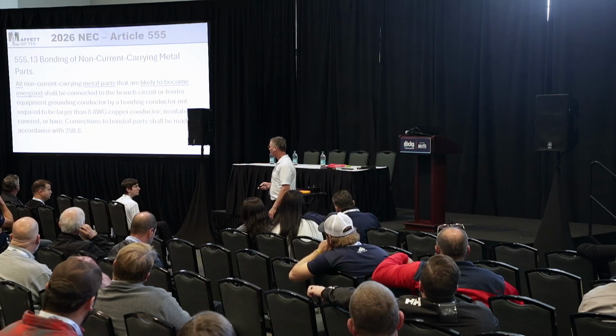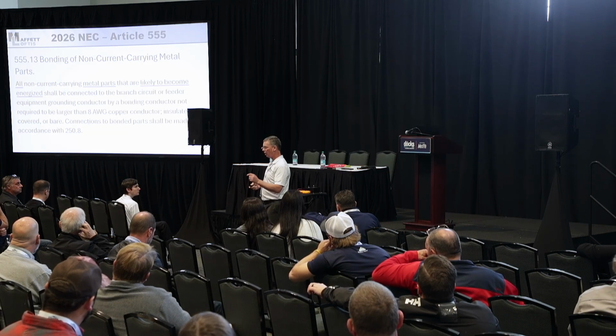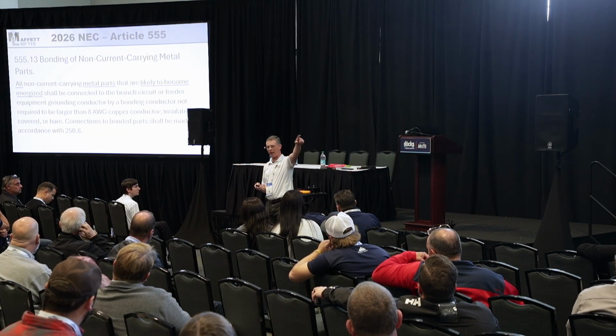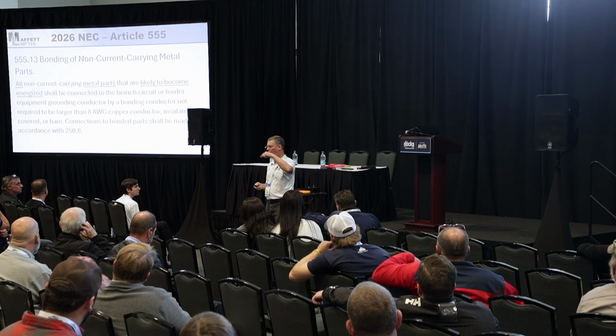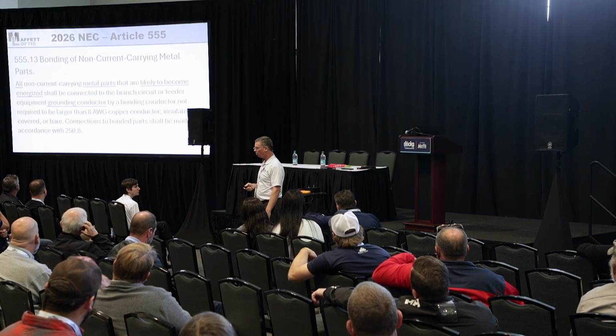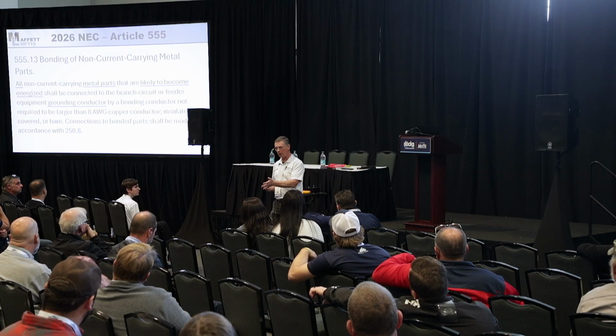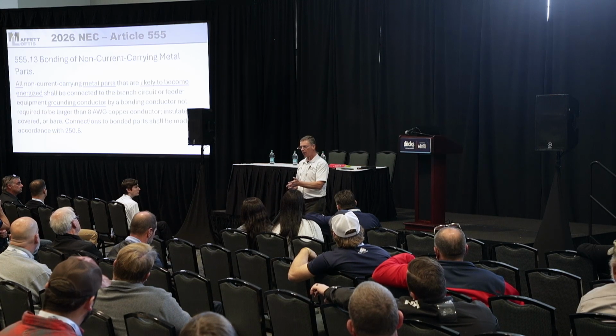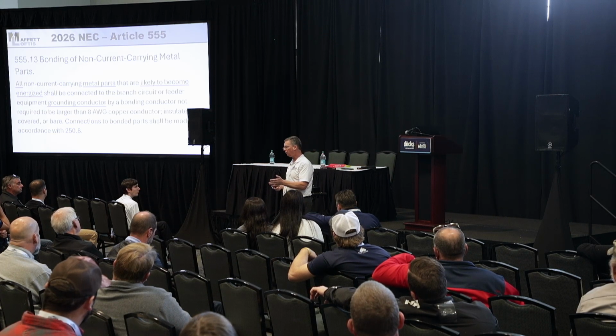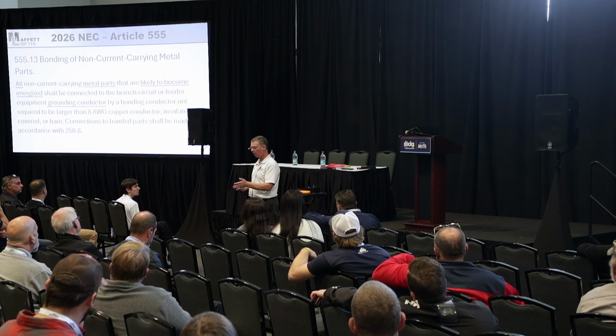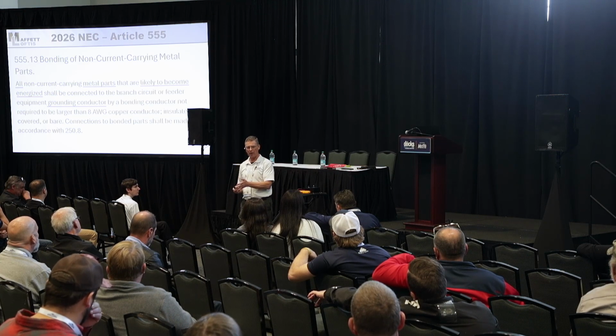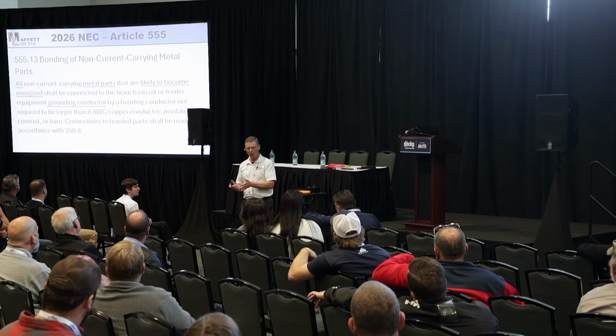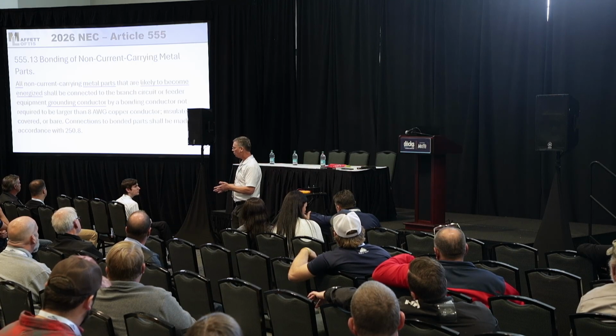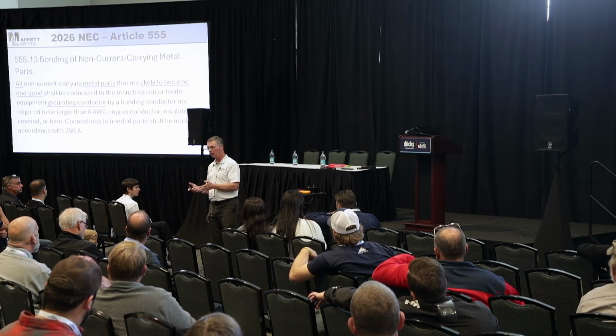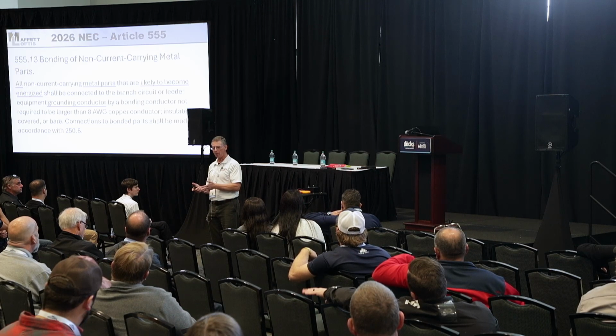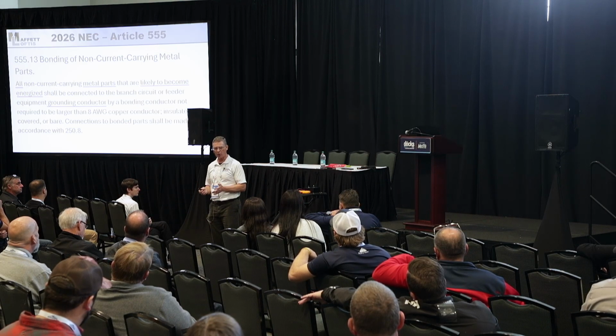a grounding point. But the previous code said that number 8 solid wire had to go back to a panel board. We're not saying that. We're saying it's going back to the equipment grounding conductor, which is really close in many instances. And the purpose of this is not to create fault current. That means if you have a 50 amp overcurrent protection, it has to pull at least 50 amps to trip that overcurrent protection. We're just trying to bond it to create enough current flow, if it did get energized, to trip the GFPE, which is about 100 milliamps. That's the only thing we're trying to do.